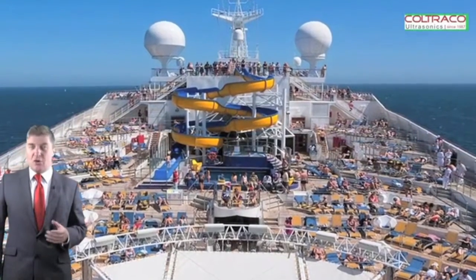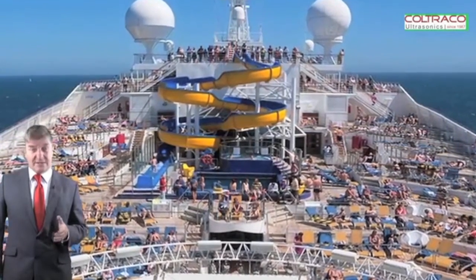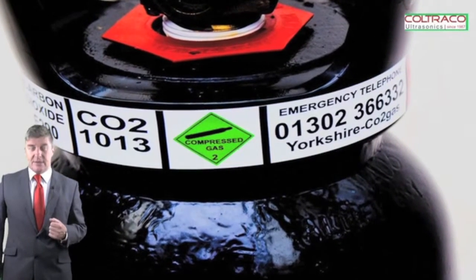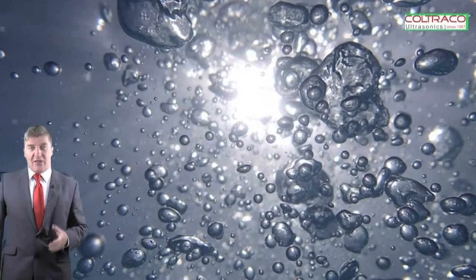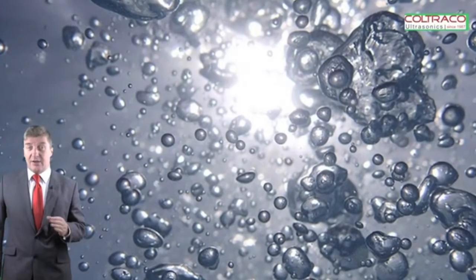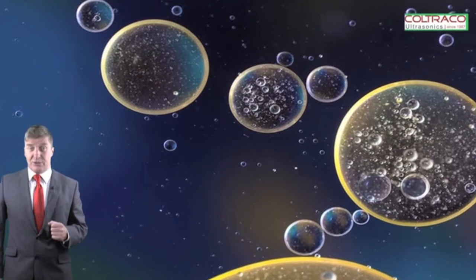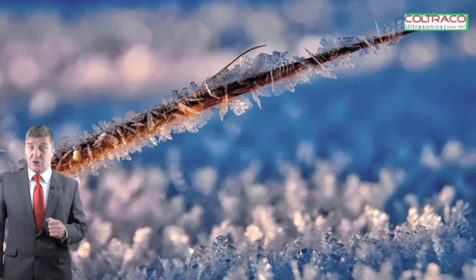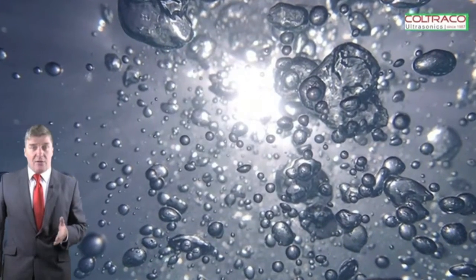How do you ensure these cylinders are full? The only true way to measure a liquefied gas is to weigh the cylinder. That is why a CO2 cylinder does not have a pressure gauge — when you pressurize CO2 to 56 bar, it liquefies because it is below its critical temperature. That's the difference between a gas and a vapor: a true gas cannot be liquefied at normal atmospheric temperatures by pressure alone, whereas vapors can; gases need cooling first.